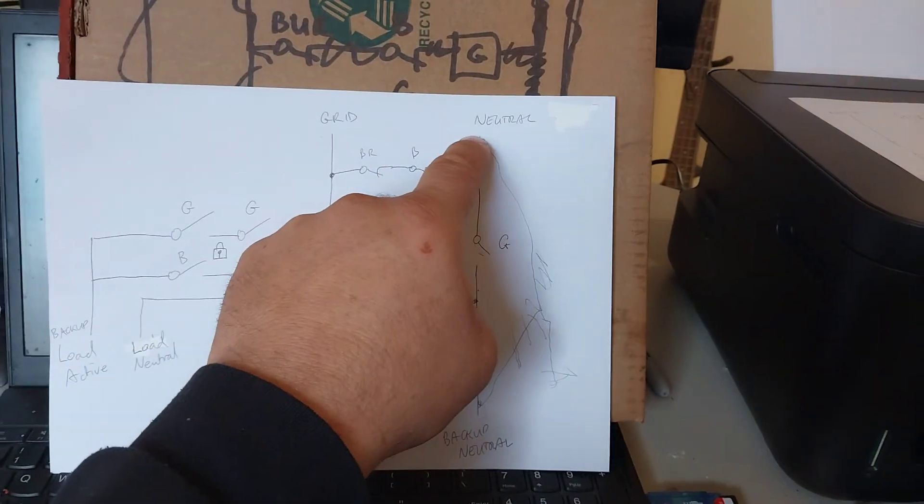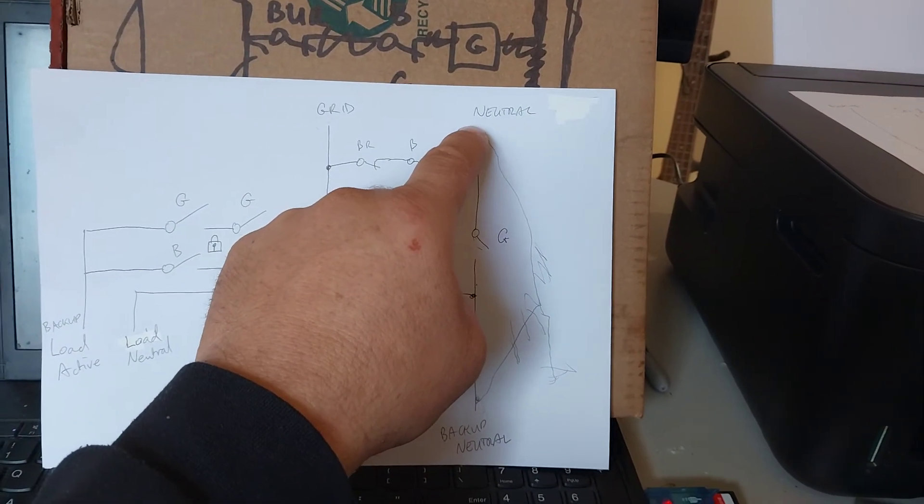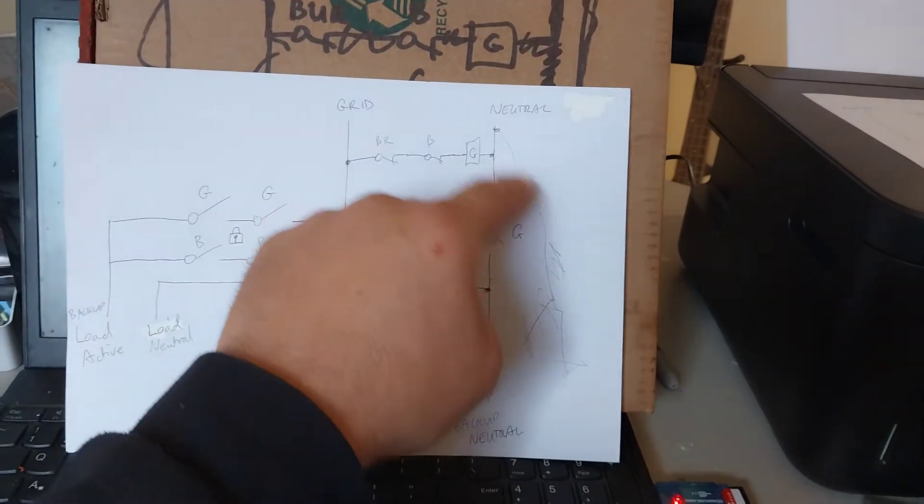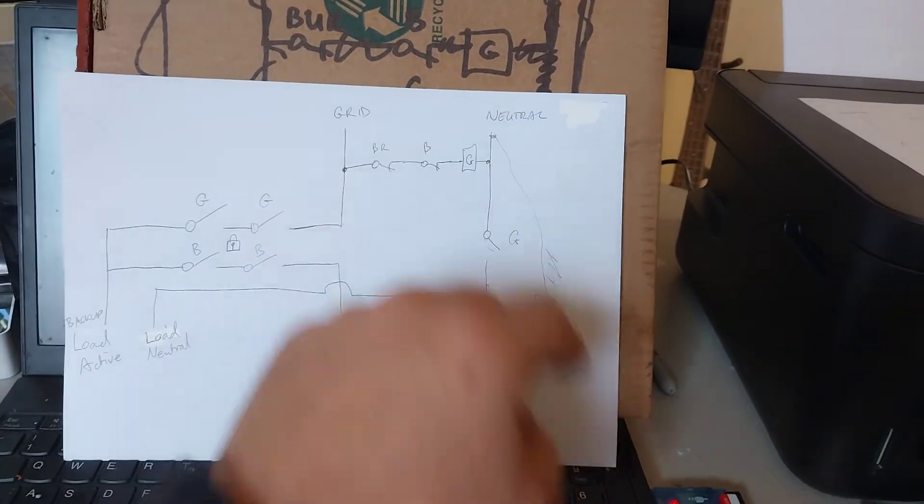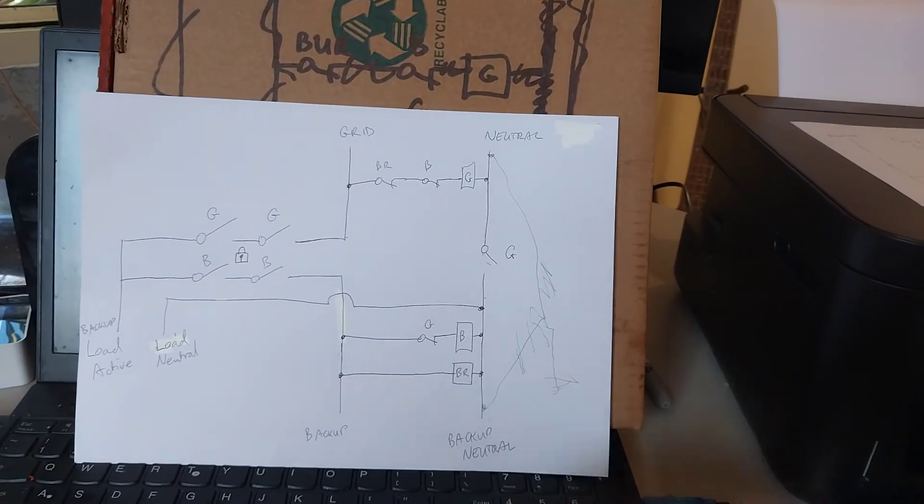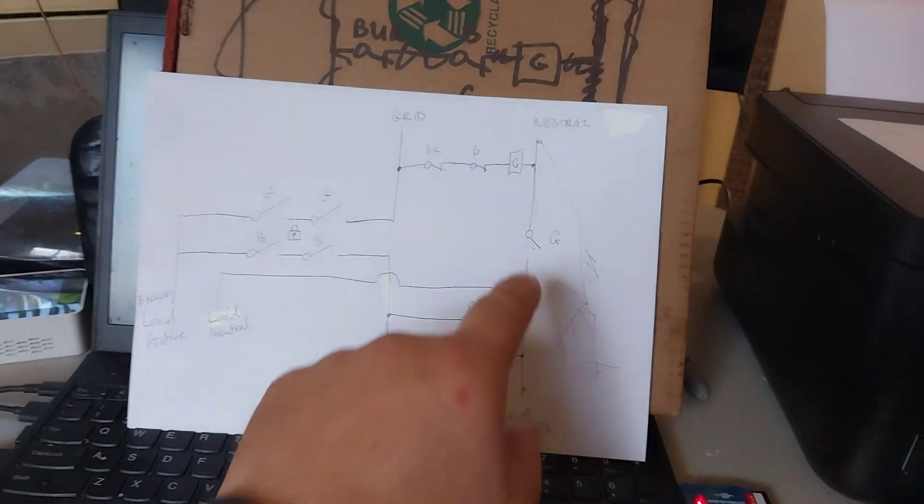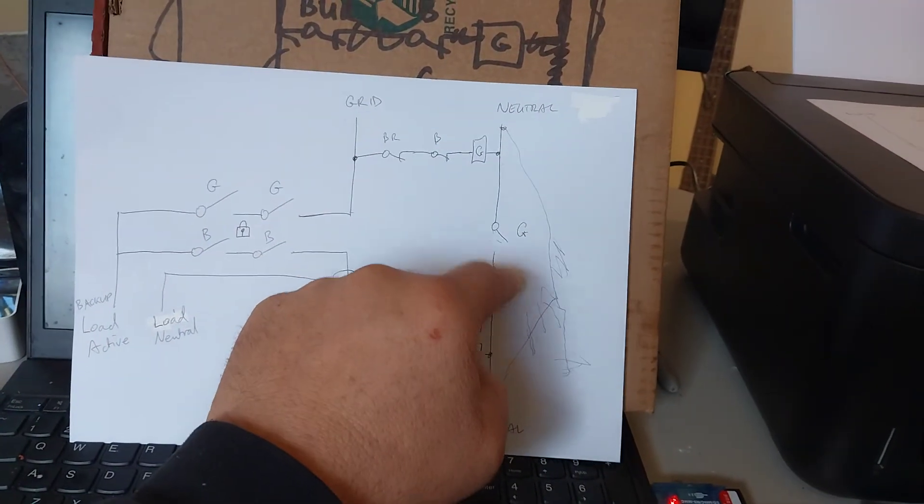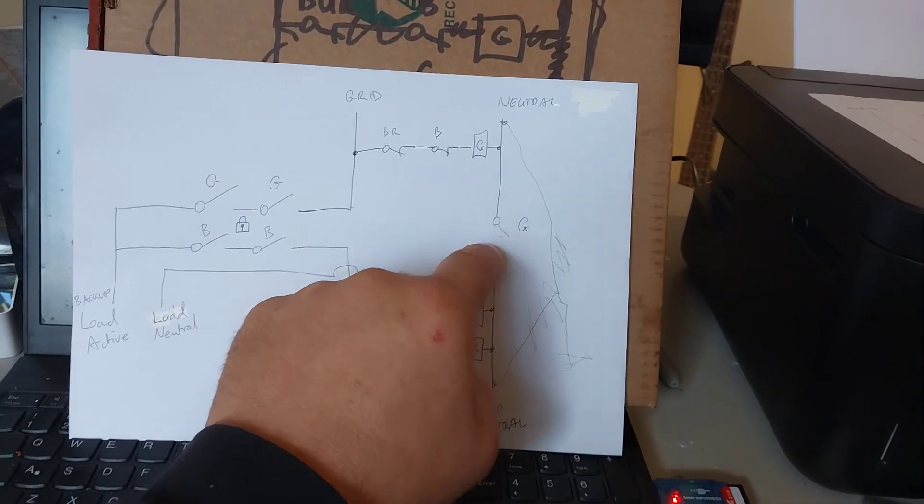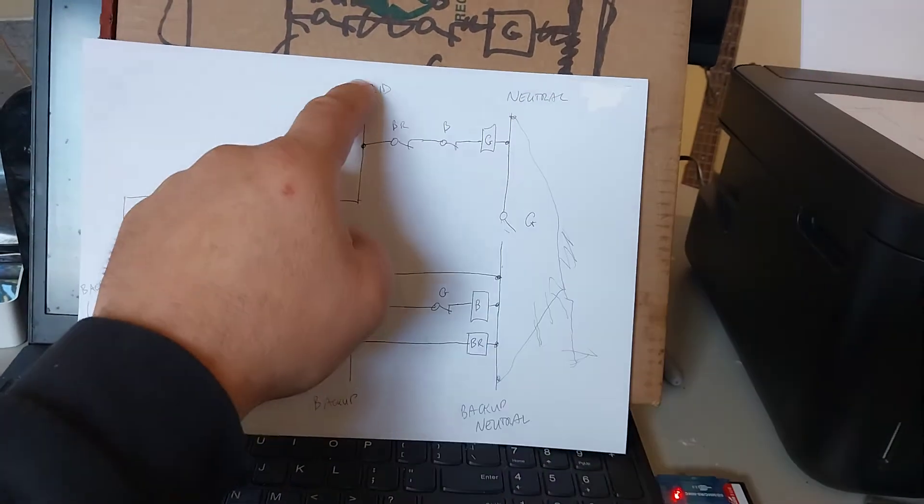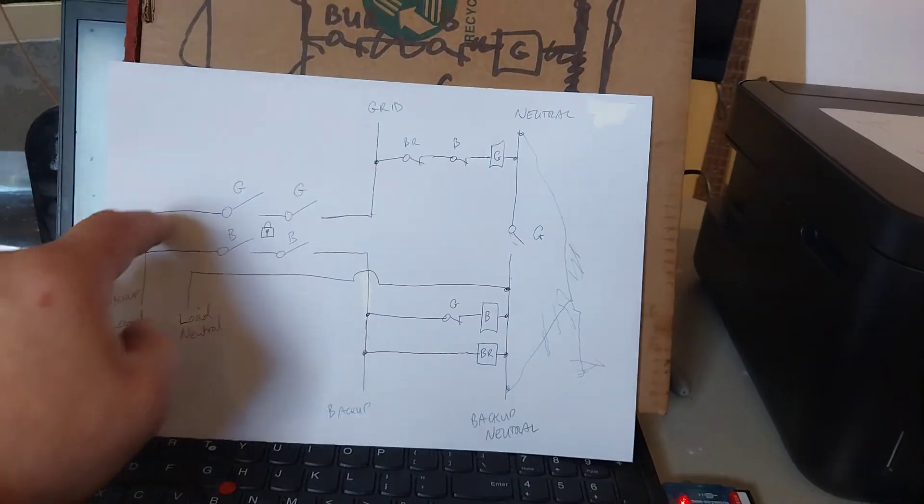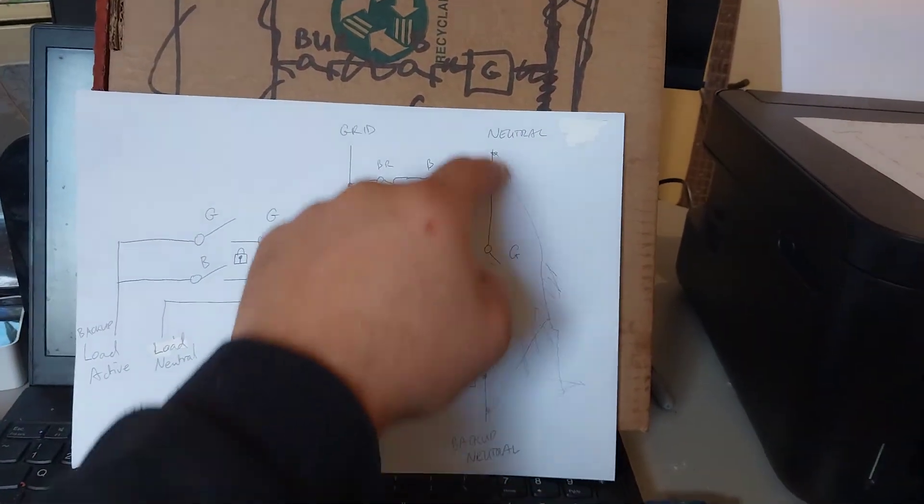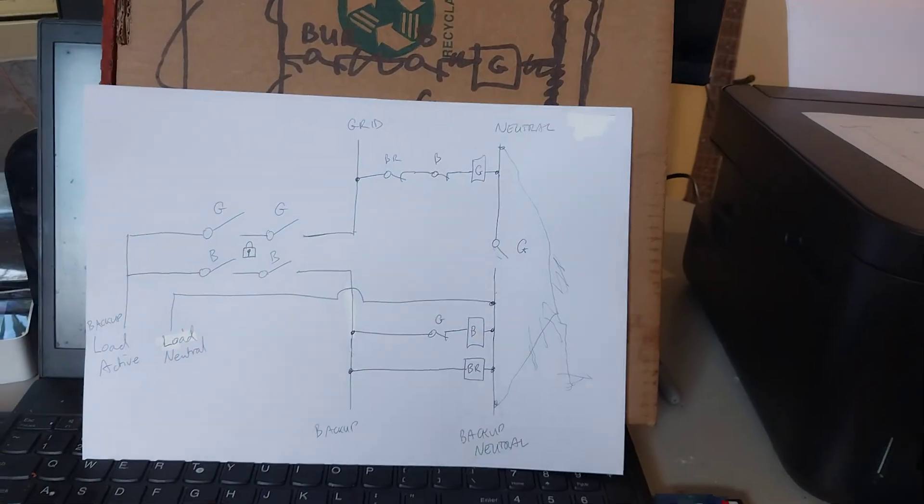And if it's already got a link between neutral and earth in the main switchboard, it'll have current flowing through the earth wire under certain circumstances. We don't want that. So that's why these two neutral bars are separate and that contact is there only for when you have no backup power and the grid is supplying your backup loads and needs to get back to the main neutral.